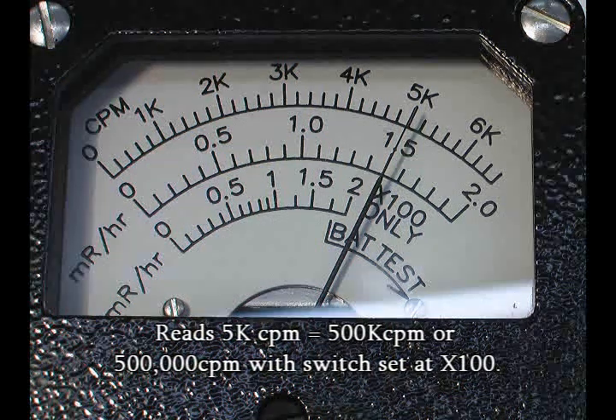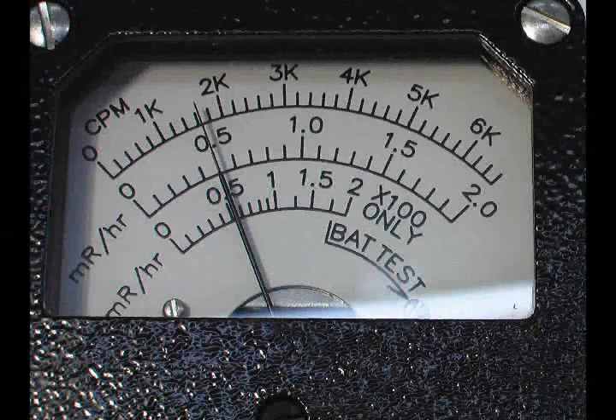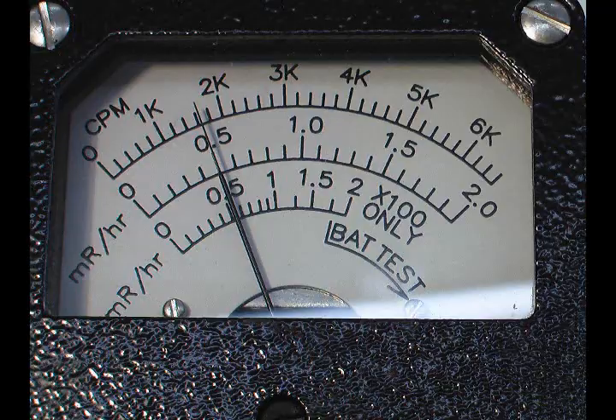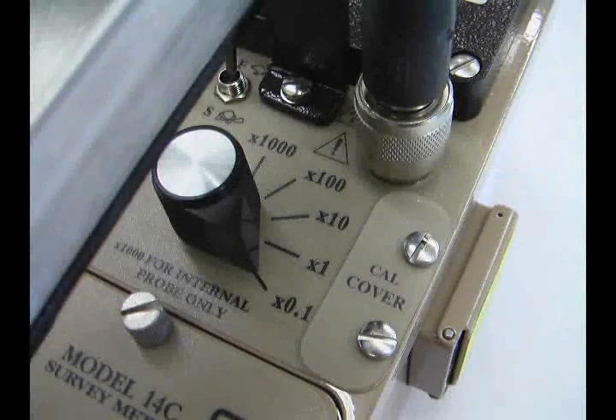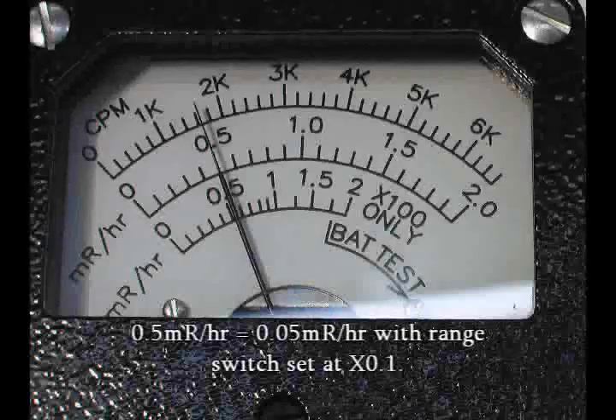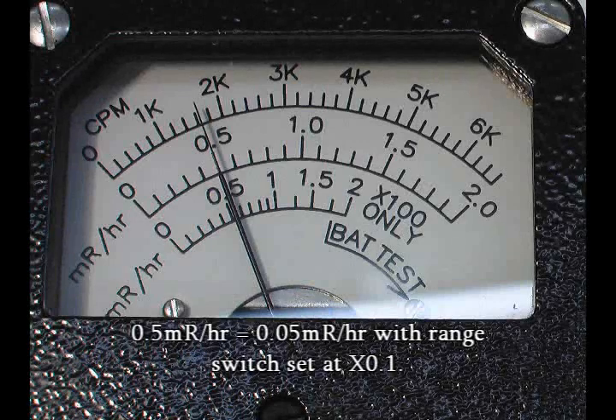Remember that this scale is not valid with the times 1000 range setting. In this example, reading the middle millirem per hour scale, the meter needle is on the 0.5 tick mark, and the range selector switch is on the times 0.1 setting. The meter reading will be 0.05 millirem per hour.